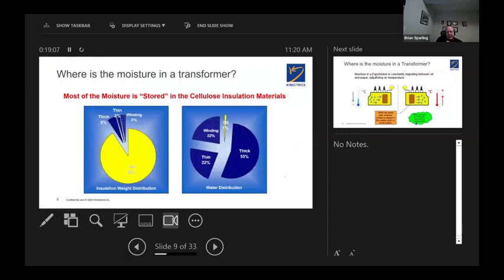Now, it brings us to where is most of the moisture in the transformer? Well, when we look at the mass of insulation materials in the transformer, typically 90% of the mass is oil, 10% of the mass is solid insulation, cellulose. And it's composed predominantly 5% of the mass is the thick blocks that hold everything together inside mechanically. 2% are the barriers between windings and at around the ends of the windings, the collars. And 3% of the mass is the actual paper wrapped around the conductors of the transformer.